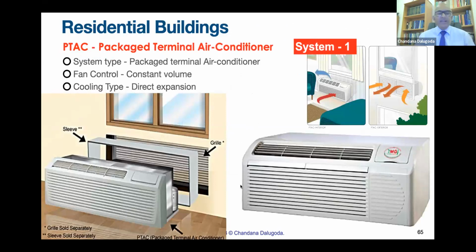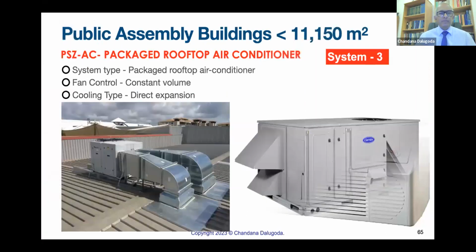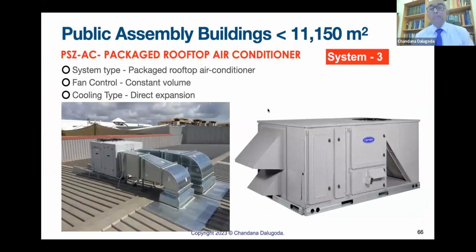Residential buildings, definitely it has to be a package terminal, either split units or window type. Public assembly buildings of 11,000 square meters or below, we must use package rooftop. Now, this is one of the best air conditioners because it is factory tested, performance guaranteed. You don't have any local involvement, no gas charging, no piping, nothing. You give the power supply, connect the ductwork, supply and return. You don't need fresh air ductwork. We don't need extract ductwork because that is built in here.